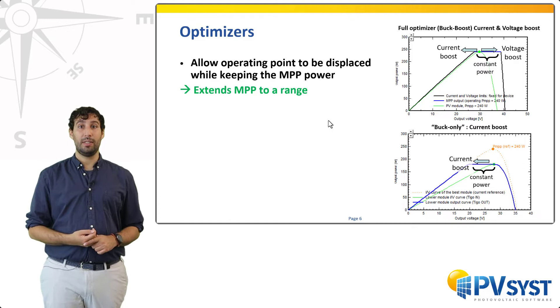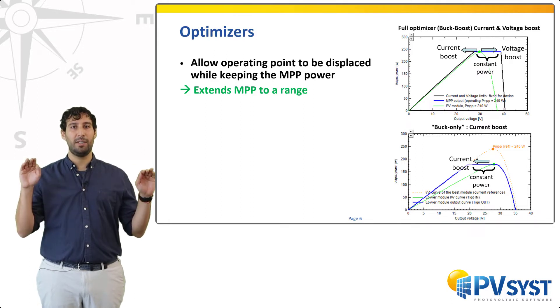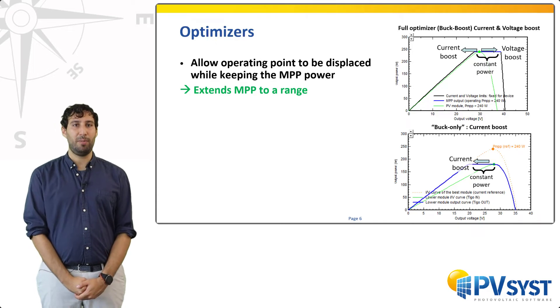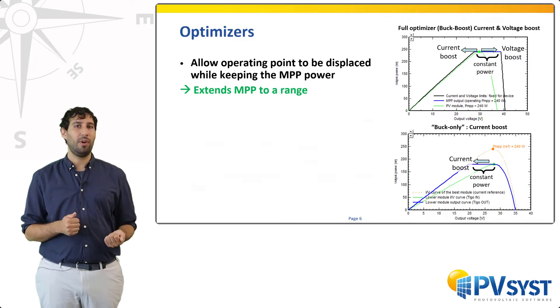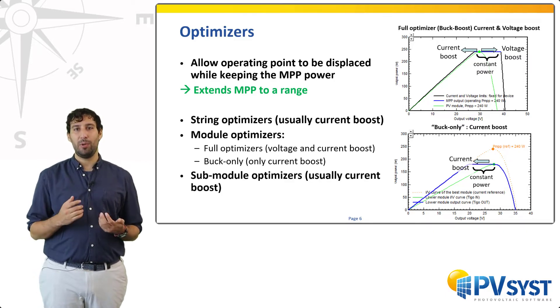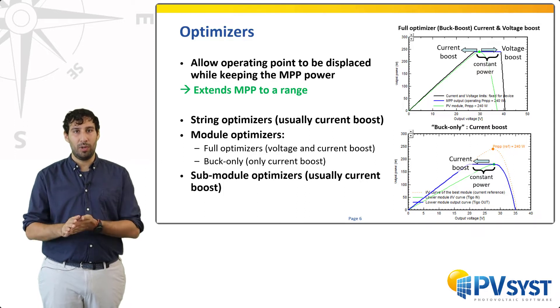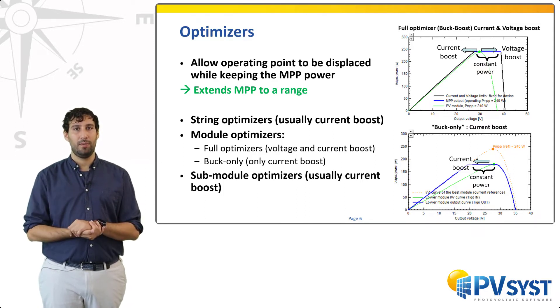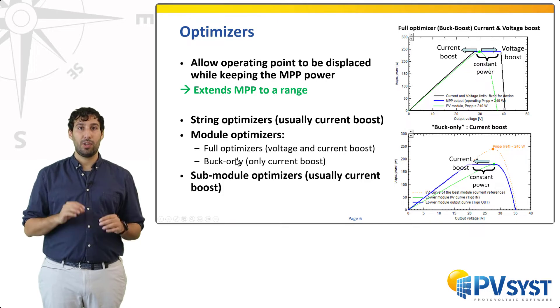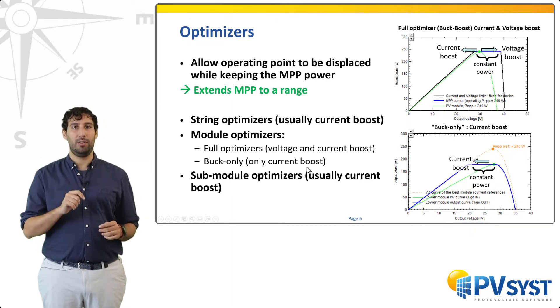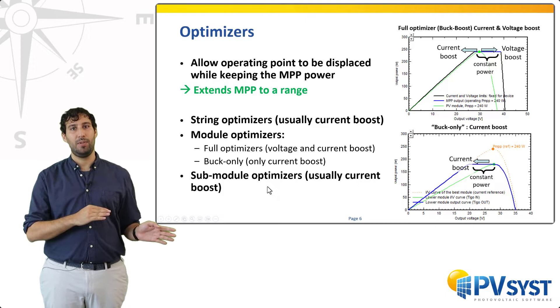In the plot, you can see the effect of an optimizer on the PV curve of a module. The MPP is extended to a flat maximum power range. There are several types of optimizers: string optimizers, that operate at the level of one or several full strings; module optimizers, which extend the MP range of modules and are then connected in series to form a string — we differentiate in PVSYST the terms buck-only, which boosts the current only, and full optimizers, with both current and voltage boost; and finally sub-module optimizers, which are integrated in the module design, with natively three optimizers in parallel per module, lessening the necessity of using bypass diodes.